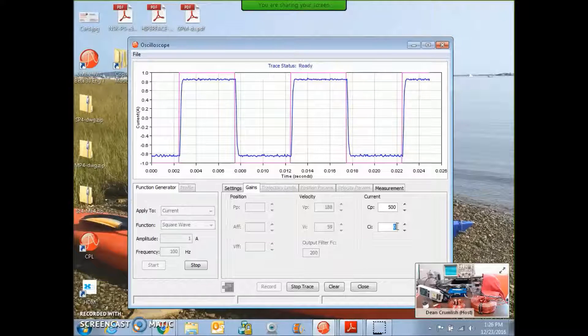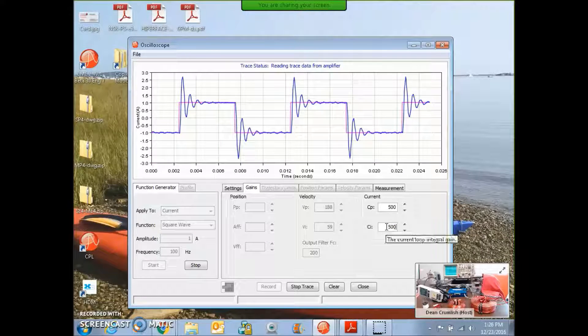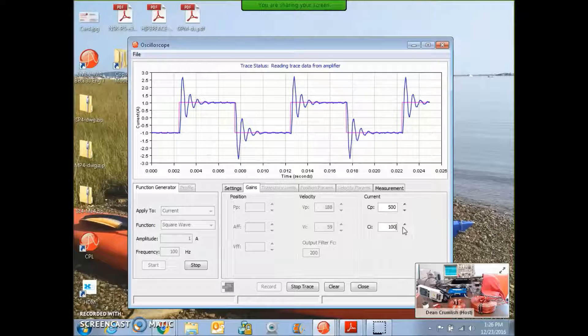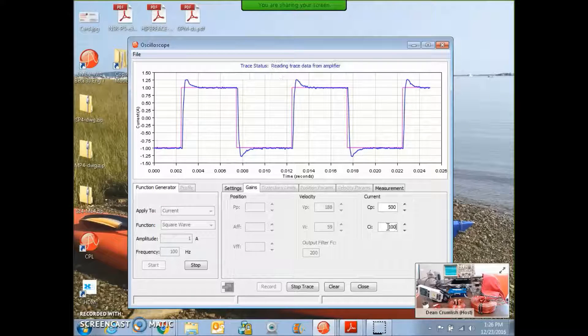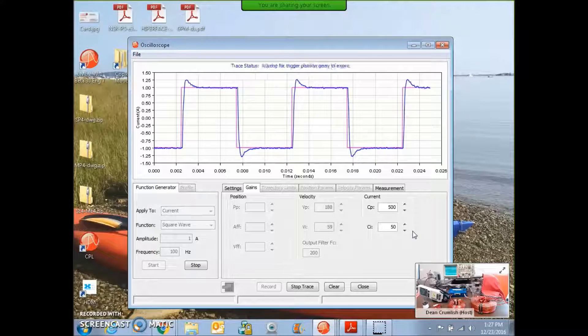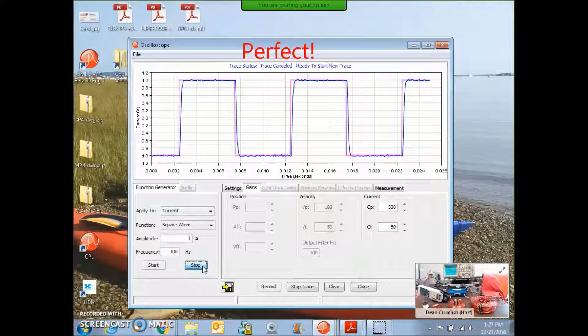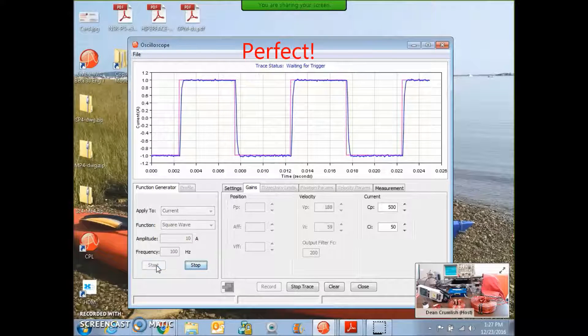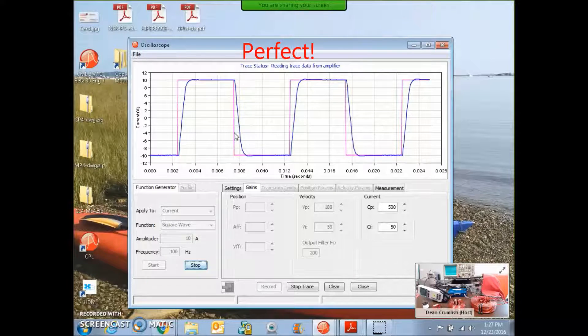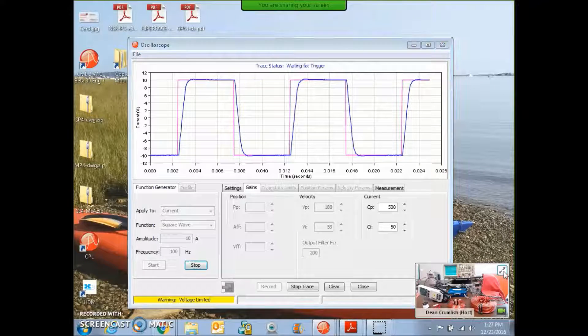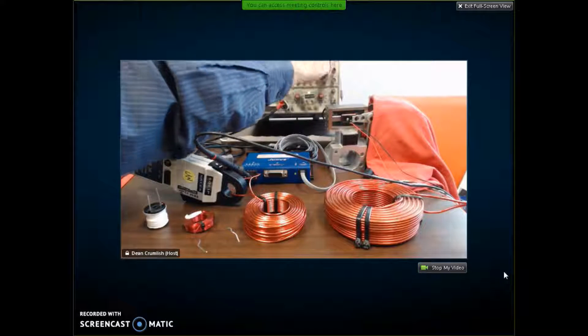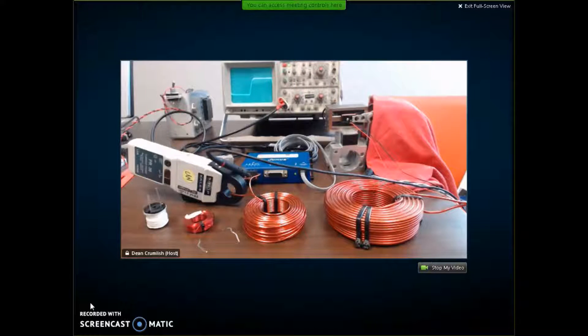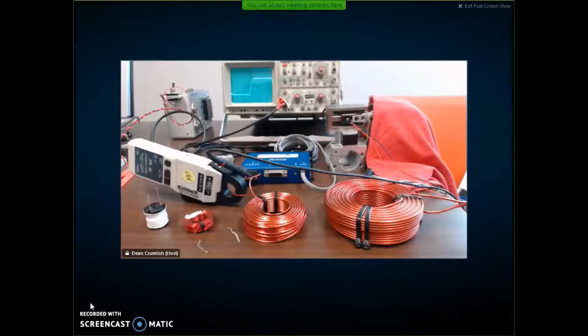And let's go for the integral term. Too much integral term is too ringy. This is a small signal tuning. We'll take a look at the large signal tuning. I'm going to give it a full 10 amps and we'll see what the step response is there. There's 10 amps of current loop. And see what the scope is doing here. There's the plus or minus 10 amp response on the scope.